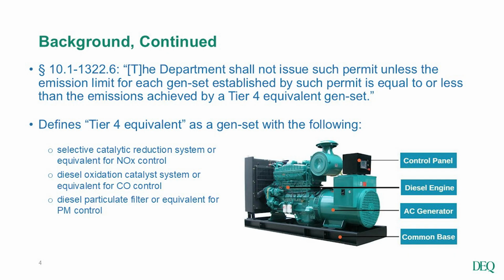This is an excerpt from 10.1-1322.6 of the Code of Virginia, which establishes that the department shall not issue such permit unless the emission limit for each genset established by such permit is equal to or less than the emissions achieved by a Tier 4 equivalent genset. It defines Tier 4 equivalent as a genset with the following controls: selective catalytic reduction system or equivalent for nitrous oxides control, diesel oxidation catalyst or equivalent for carbon monoxide control, as well as a diesel particulate filter or equivalent for particulate matter.